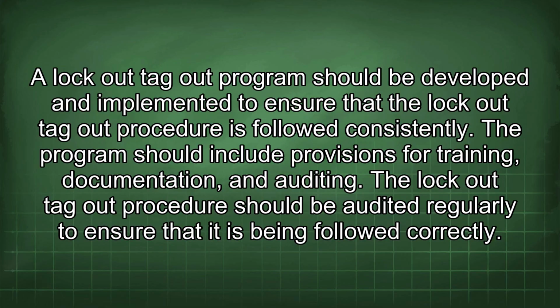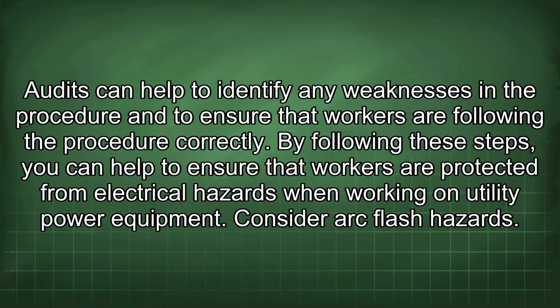A lockout tagout program should be developed and implemented to ensure that the lockout tagout procedure is followed consistently. The program should include provisions for training, documentation, and auditing. The lockout tagout procedure should be audited regularly to ensure that it is being followed correctly. Audits can help to identify any weaknesses in the procedure and to ensure that workers are following the procedure correctly. By following these steps, you can help to ensure that workers are protected from electrical hazards when working on utility power equipment. Consider arc flash hazards.